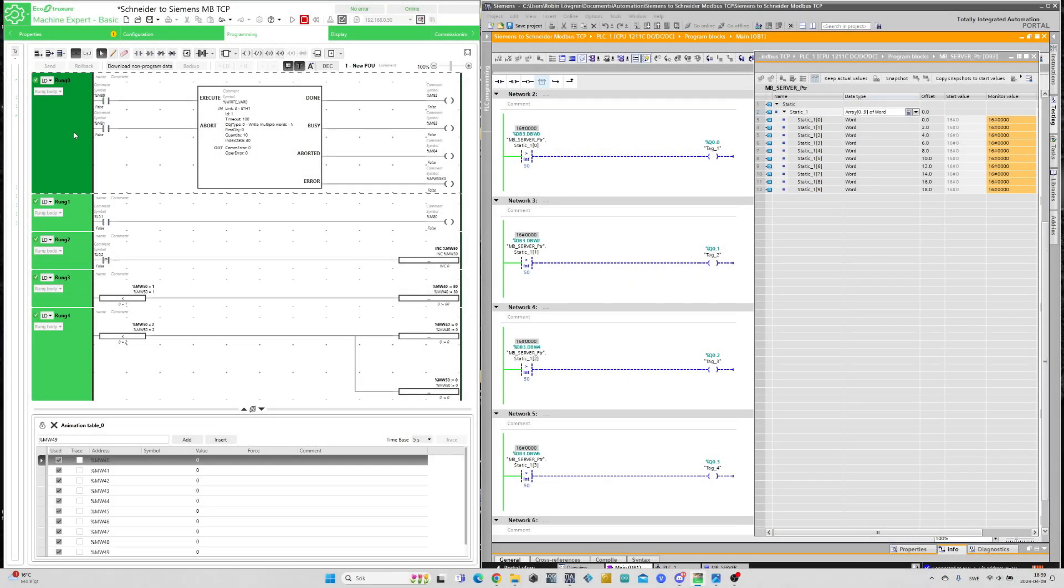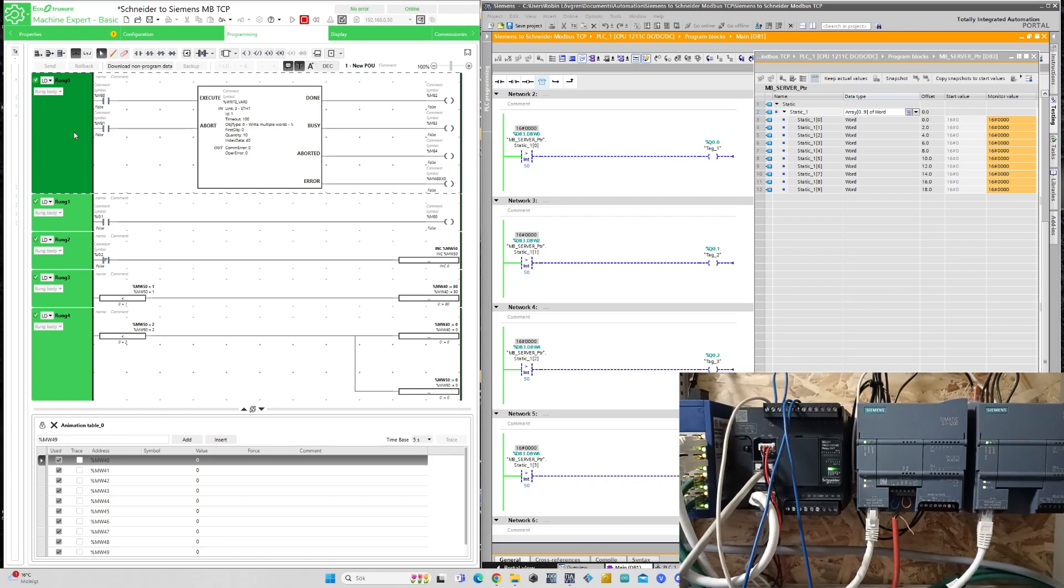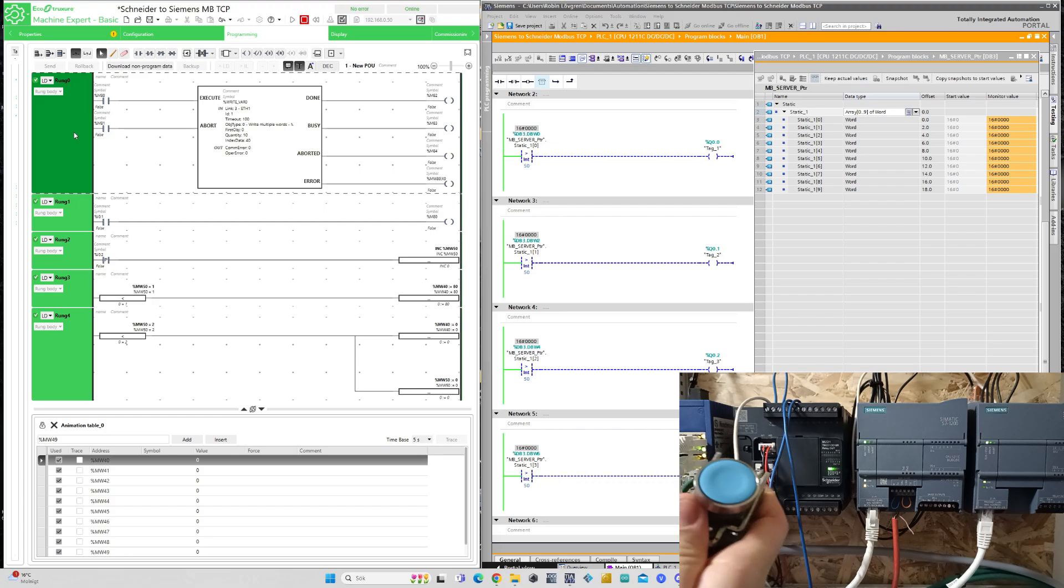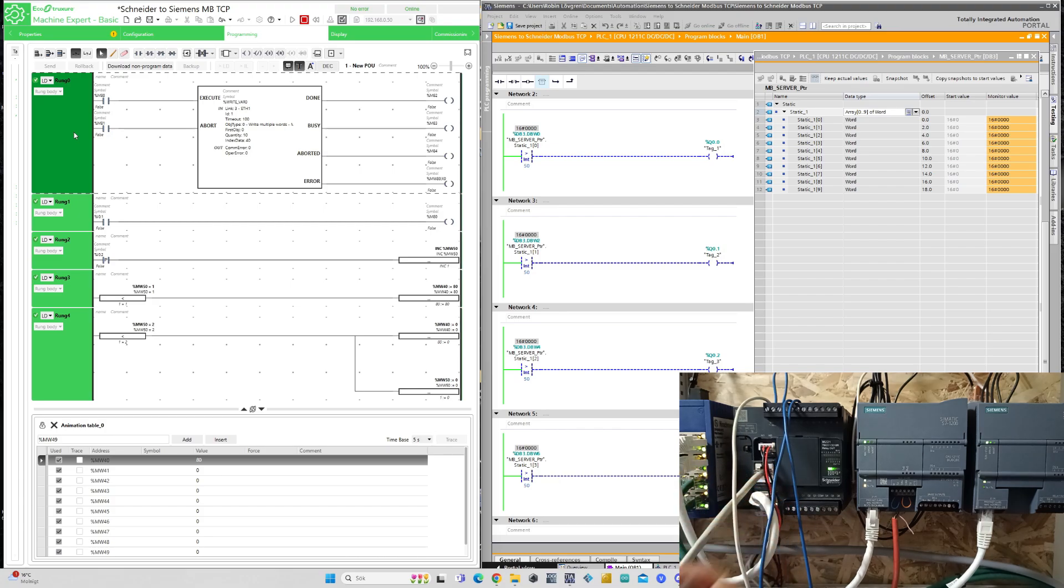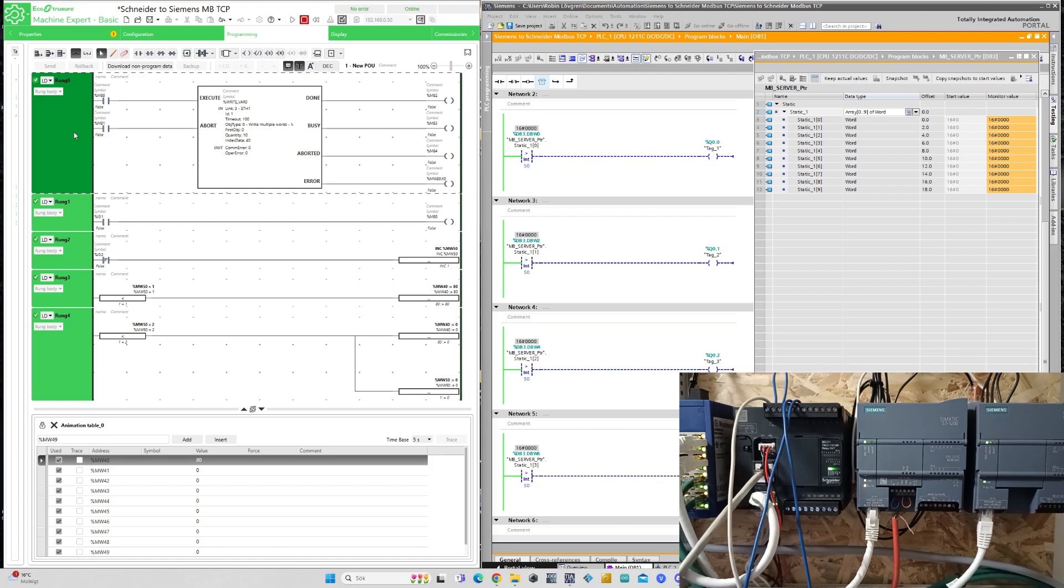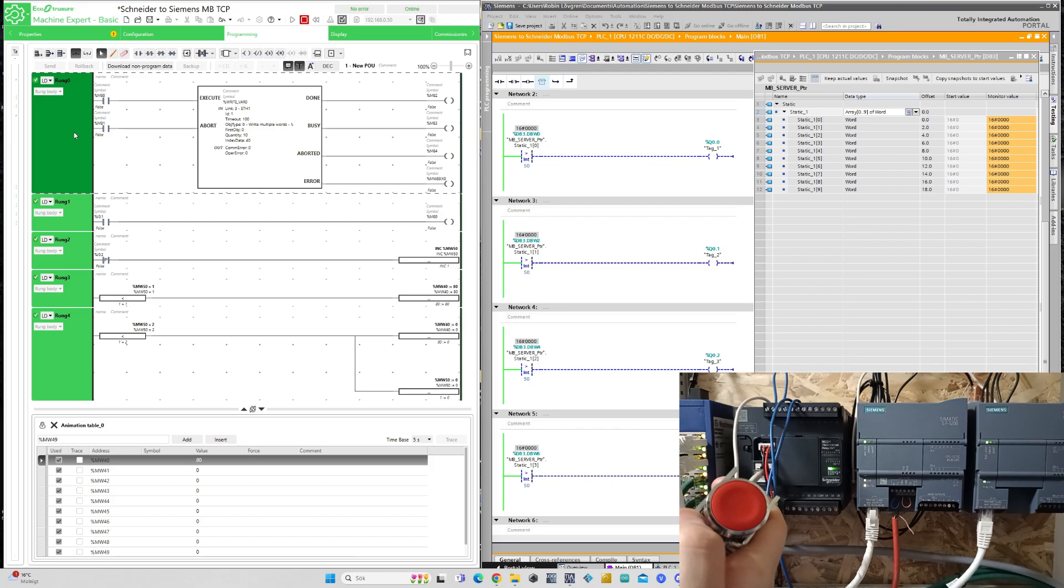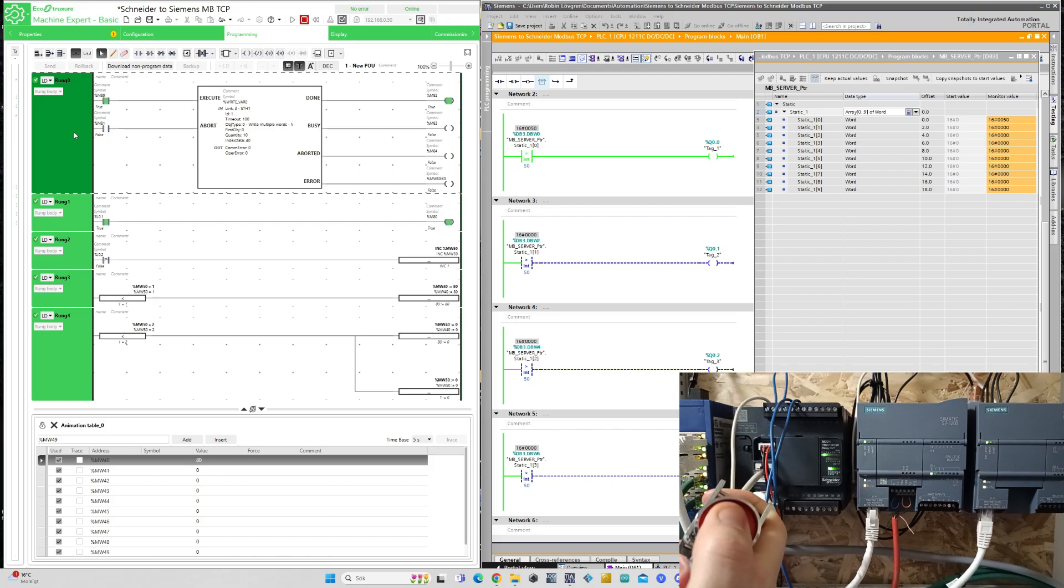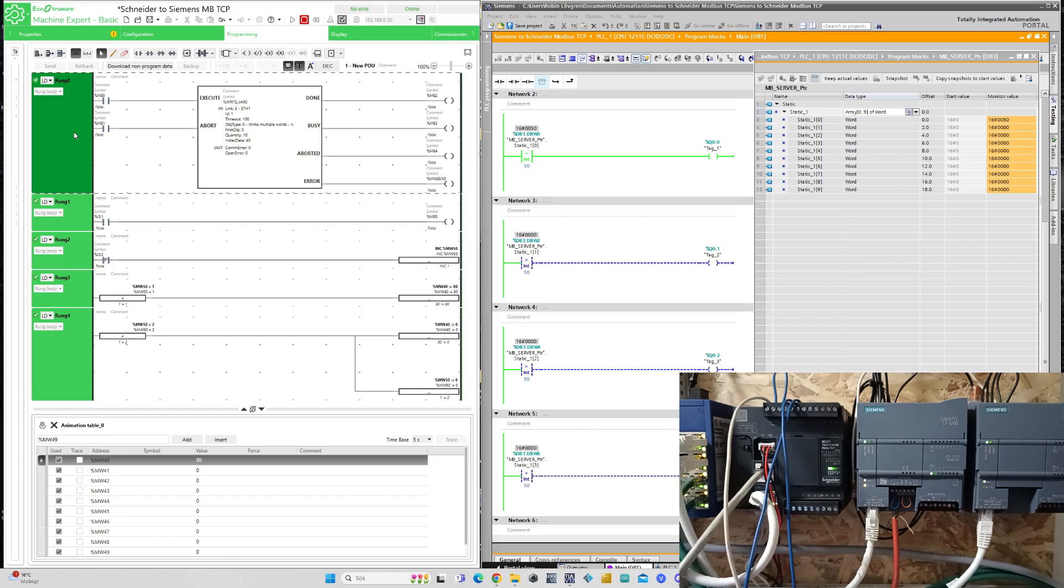I am now online and monitoring both the Schneider and Siemens PLC. If I now press my blue push button once I will add the value 80 to memory word 40. If I then press my red button it will execute and make a request to the Siemens PLC and it will receive the value to its first Modbus address and output number 0 will turn on.